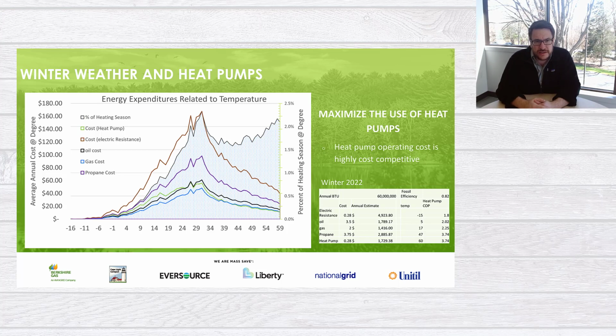Looking at this, we really spend the vast majority of our winter time right around 30 degrees-ish. Below 30 degrees, there certainly are double-digit hours, and a few single-digit hours. But by the time we're in sub-zero temperatures, there's really a non-existent heating load, typically just a few hours overnight while people are sleeping. So that isn't really what we're trying to design a heating system for, an all-time extreme of negative 16 degrees.